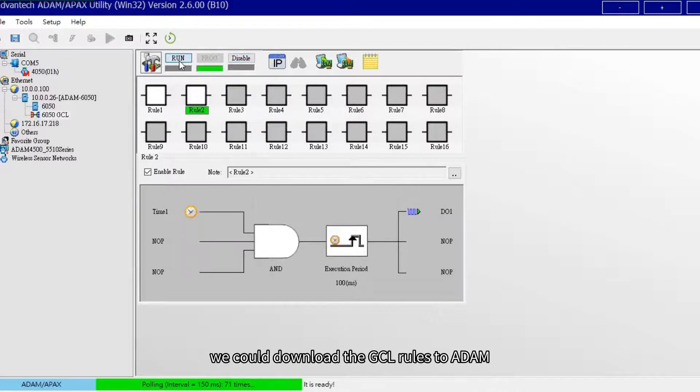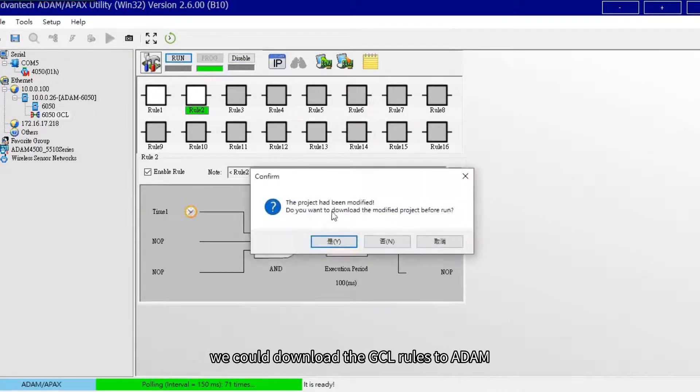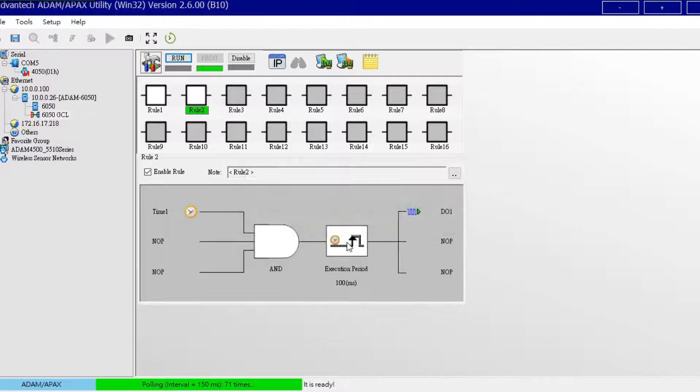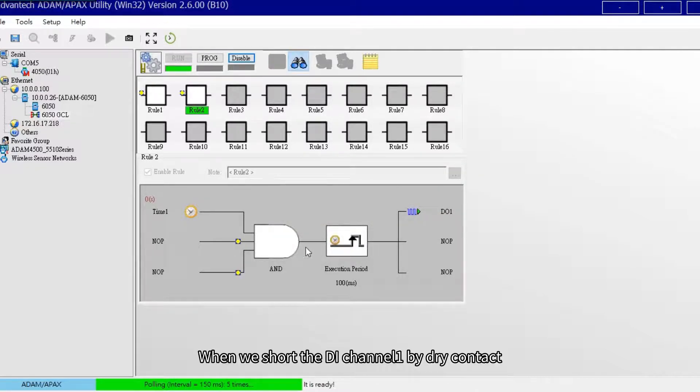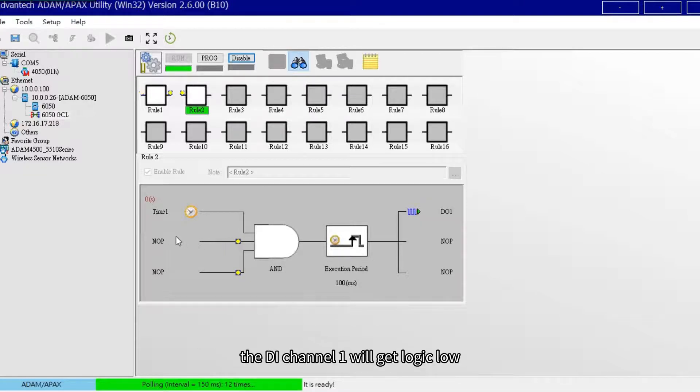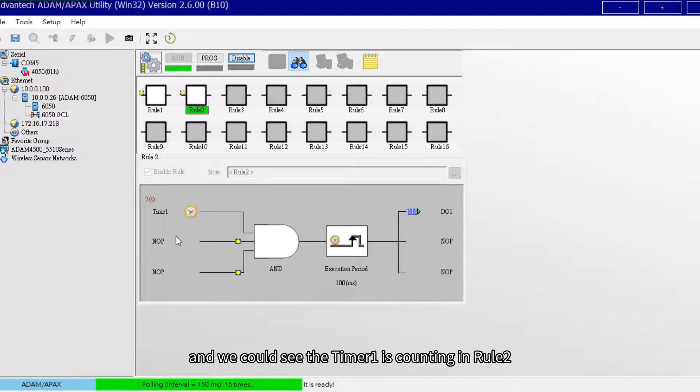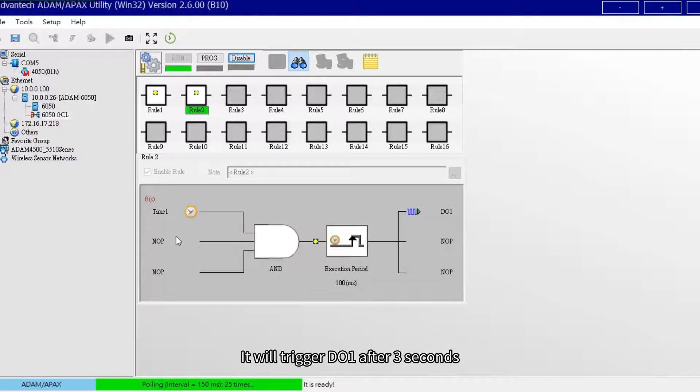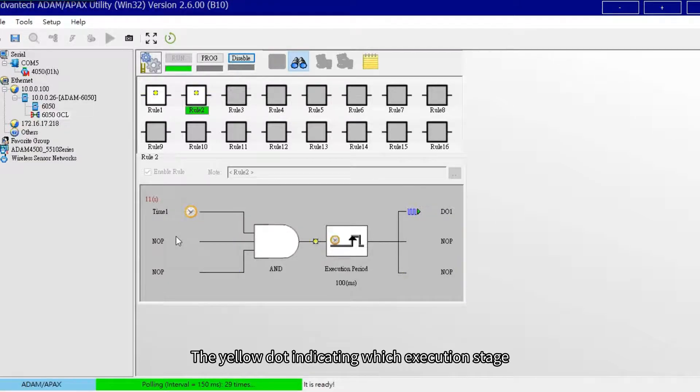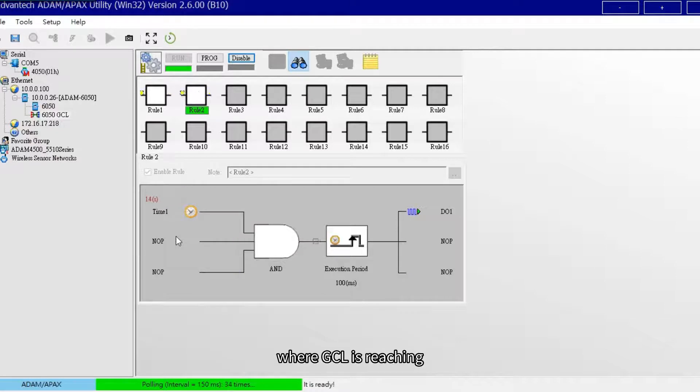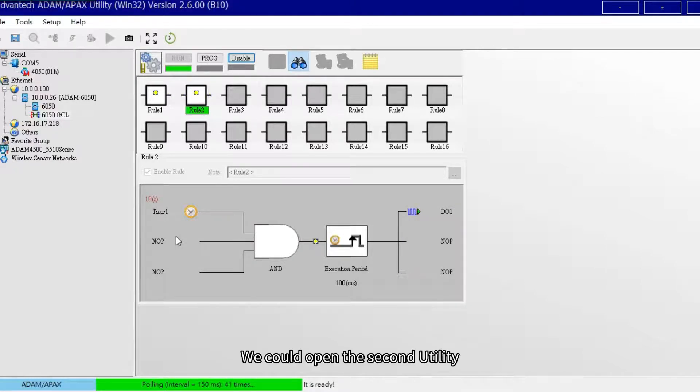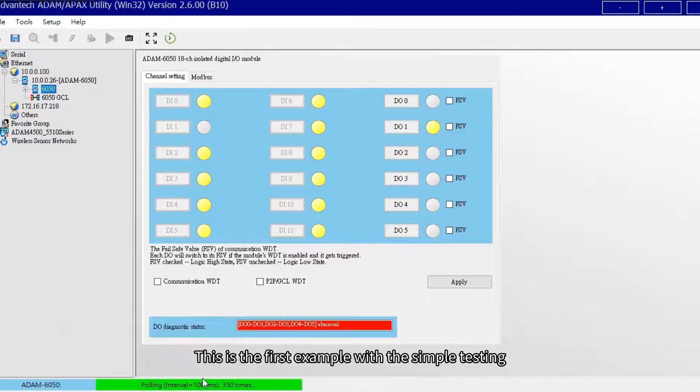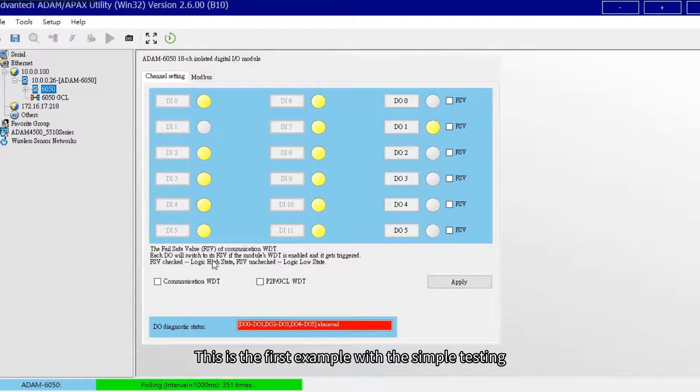After setting the rules, we could download the GCL rules to ADAM and run GCL project. When we short the DI channel 1 by dry contact, the DI channel 1 will get logic low, and we could see the timer 1 is counting in Rule 2. It will trigger DO1 after 3 seconds. The yellow dot indicating which execution stage where GCL is reaching. We could open the second utility to check the result of GCL. This is the first example with the simple testing to learn the GCL function.